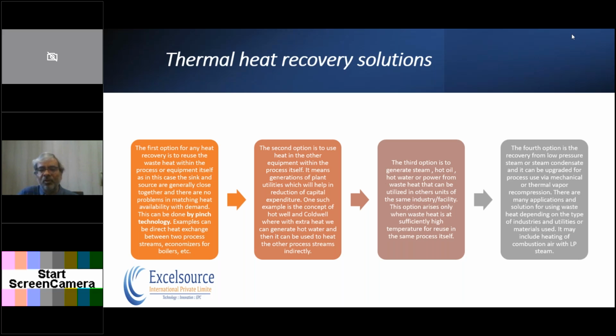Now if we have some hot water available in the plant, and we take this heat to boiler feed water heating applications, we can save the steam given to the boiler deaerator, and we can increase the overall efficiency of the boiler. So that's the second option, where a hot well and a cold well can be installed and that heat can be utilized.